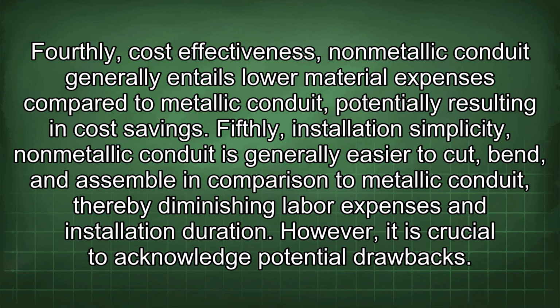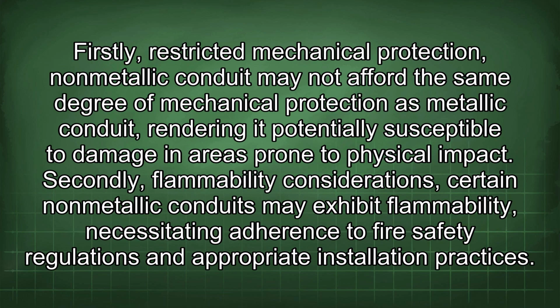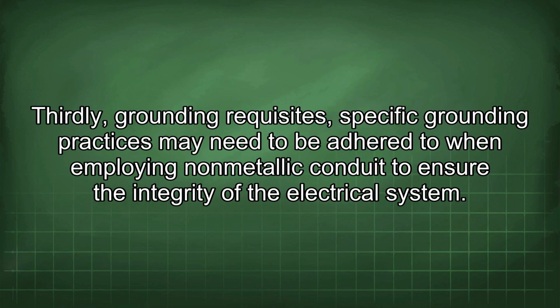However, it is crucial to acknowledge potential drawbacks. Firstly, restrictive mechanical protection. Non-metallic conduit may not afford the same degree of mechanical protection as metallic conduit, rendering it potentially susceptible to damage in areas prone to physical impact. Secondly, flammability considerations. Certain non-metallic conduits may exhibit flammability, necessitating adherence to fire safety regulations and appropriate installation practices. Thirdly, grounding requisites.